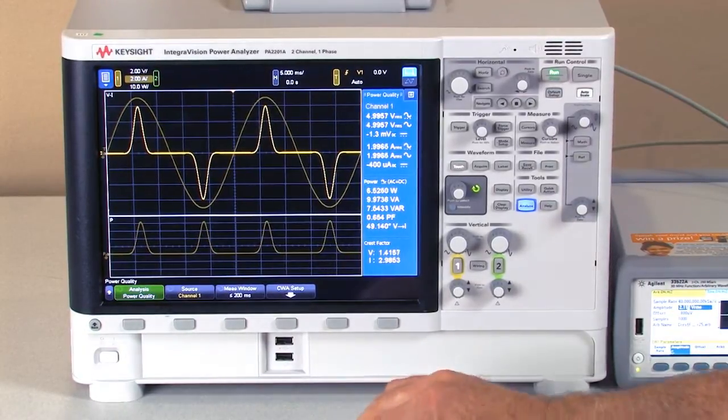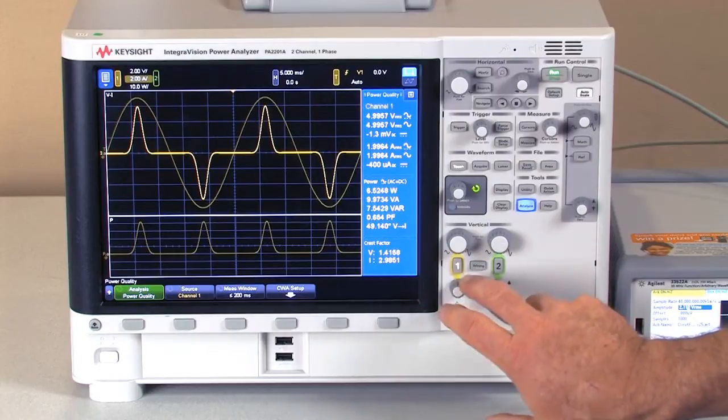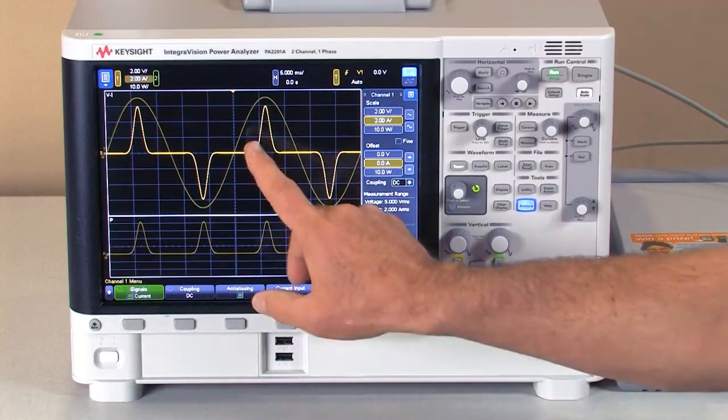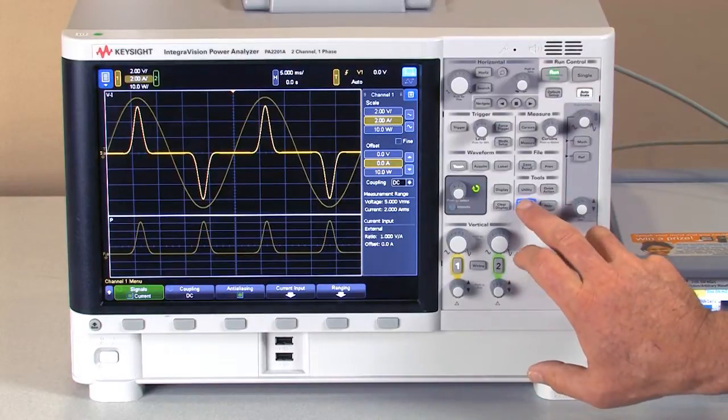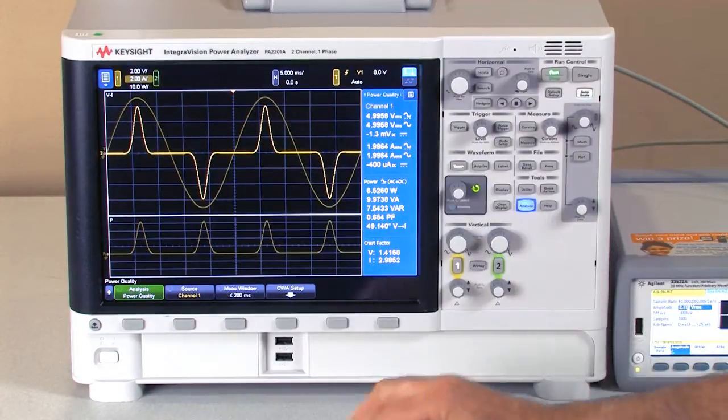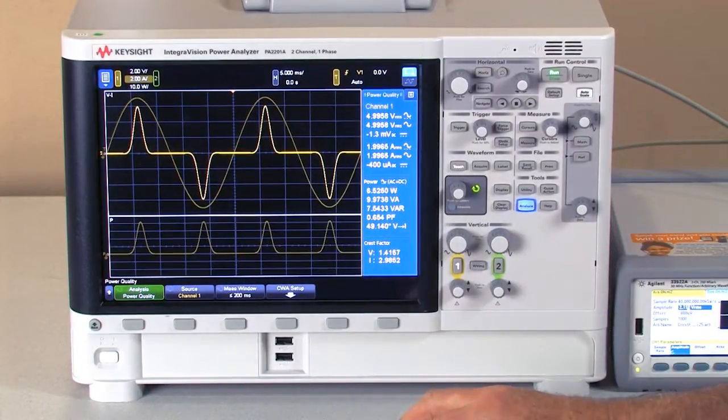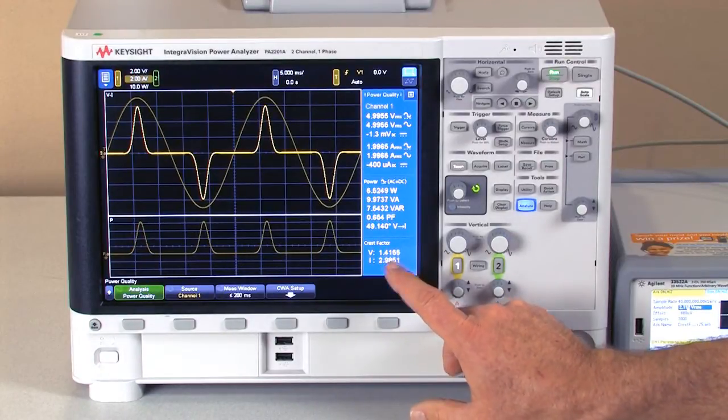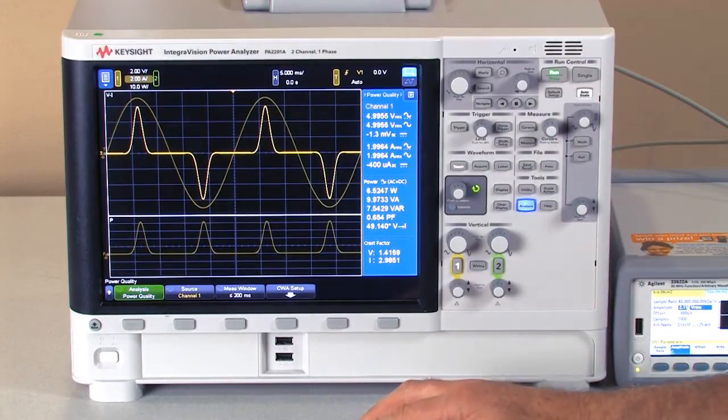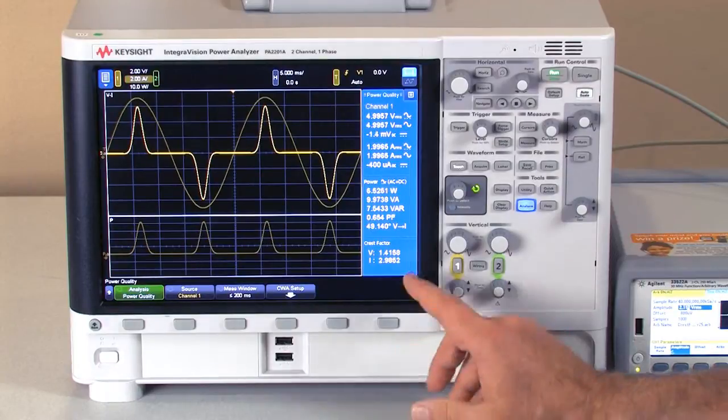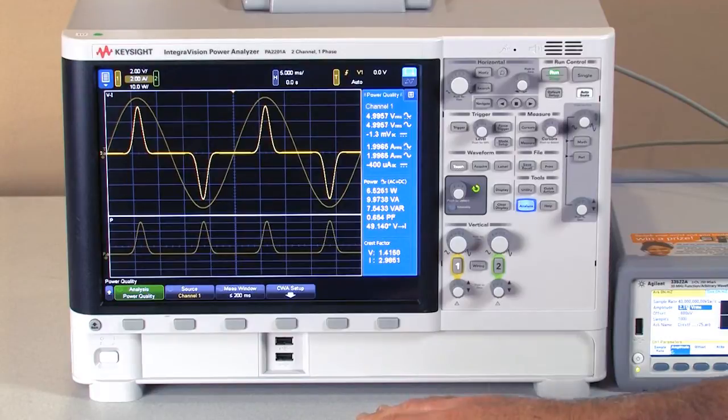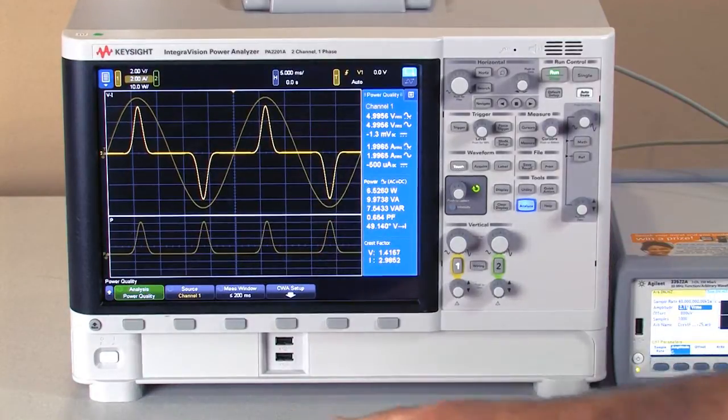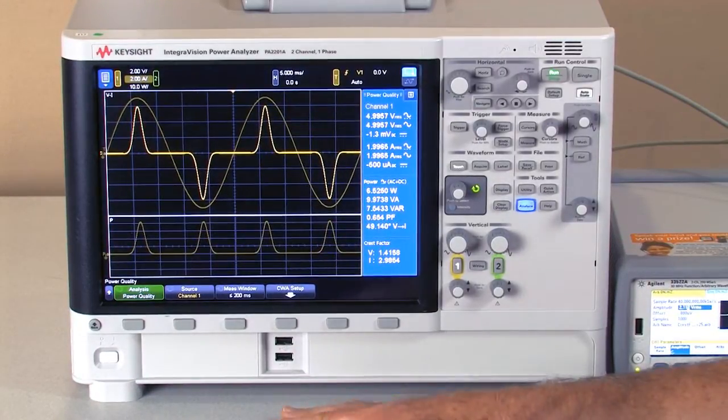So as you can see on this particular setup, I am actually measuring the current waveform on my 2 amp range and I have a full-scale 2 amp signal with a crest factor of 2.985, right at a crest factor of 3, and you can see that on the waveform as the signal just crests at 6 amps peak.